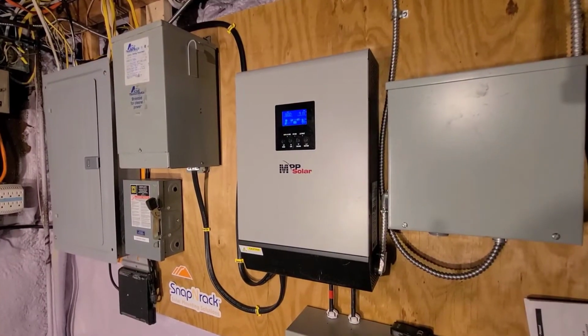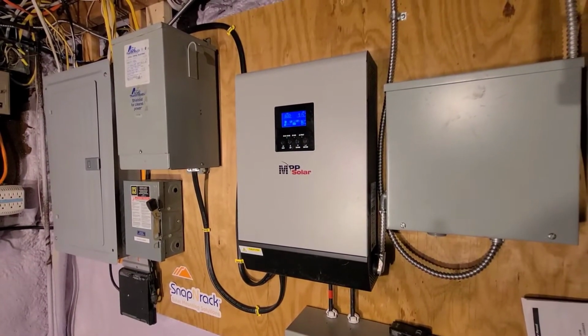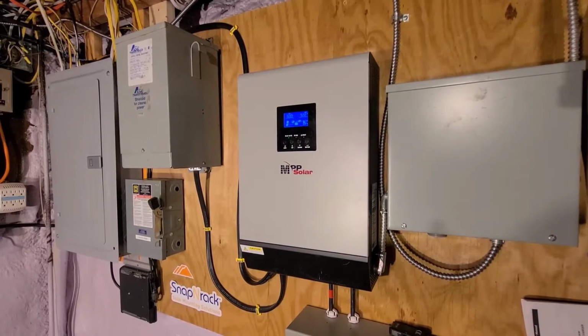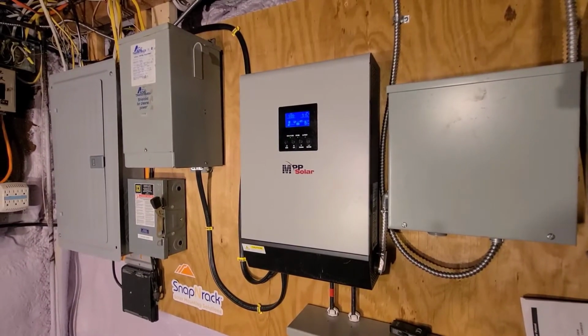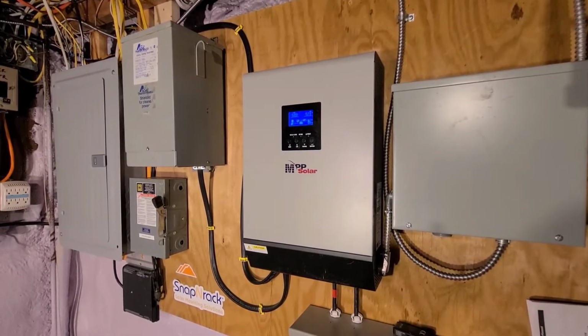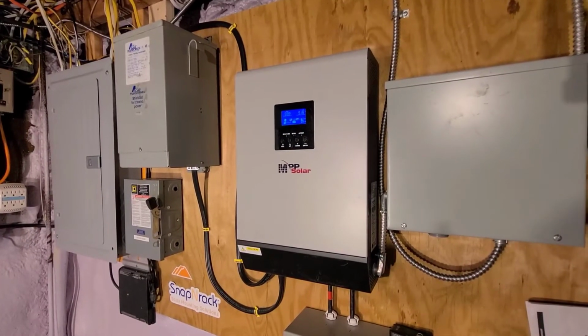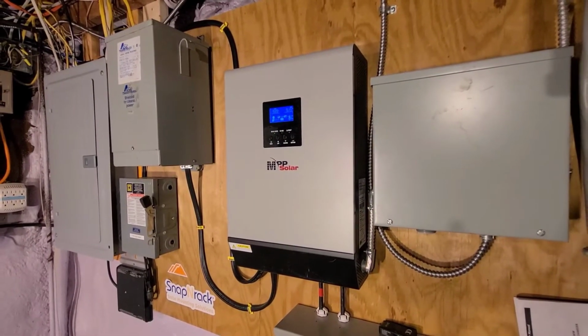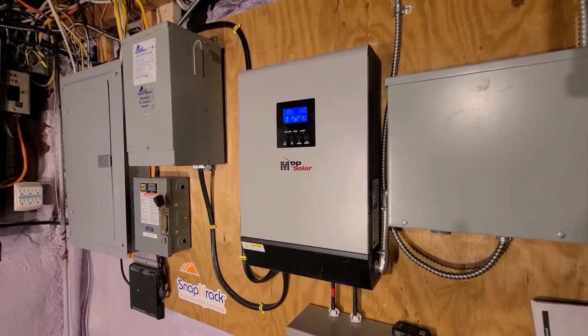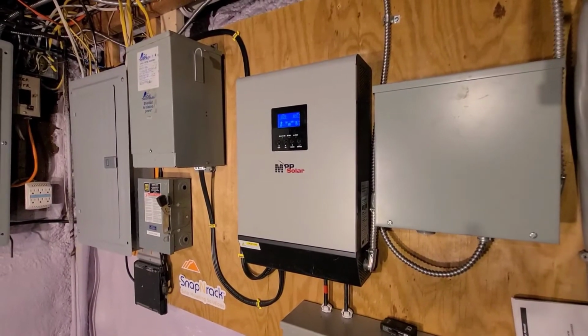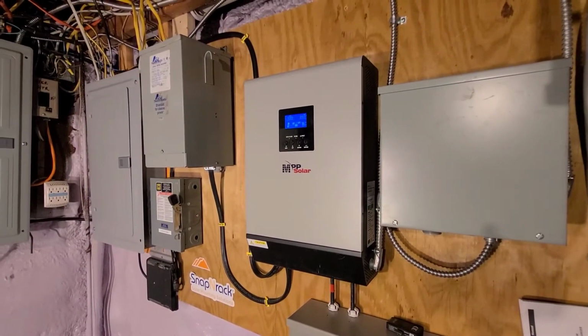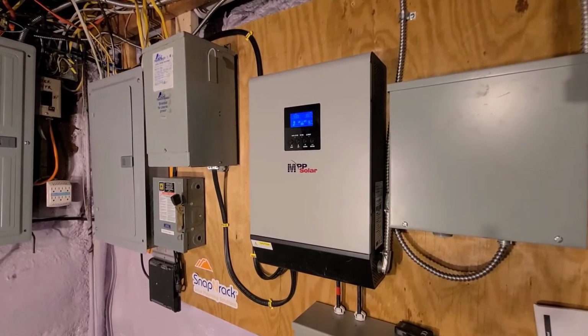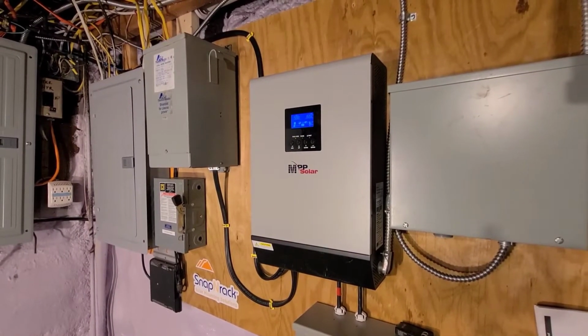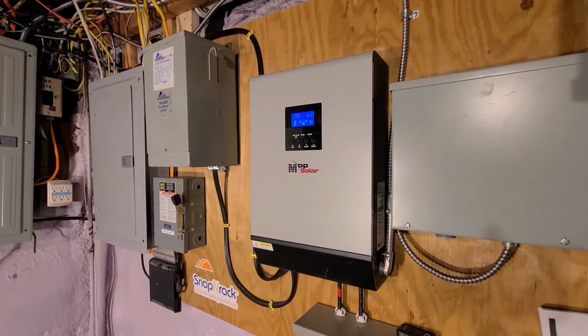We found out yesterday that this does accept my small cheap generator input as well. That does charge the battery off of it and switch over to it and run the house off of it, which is pretty cool. MPP Solar does say you should use an inverter type generator, one larger than the output of the inverter, so you don't overload anything, but it does work with a cheaper generator that's not of amazing quality.